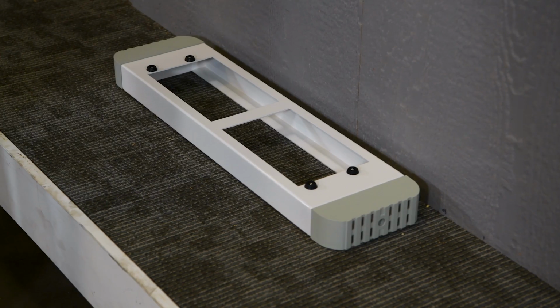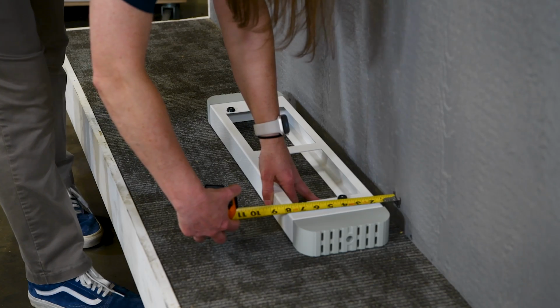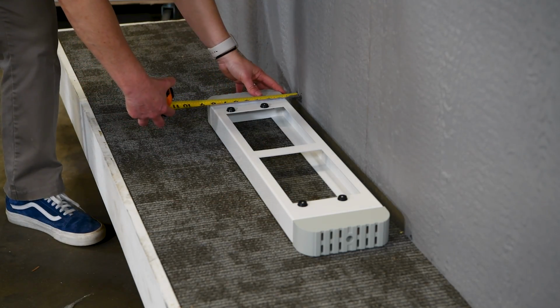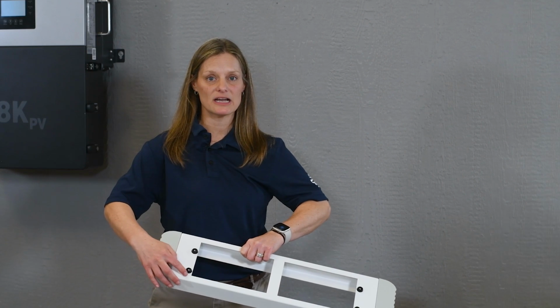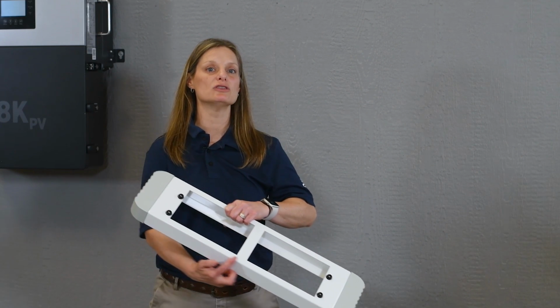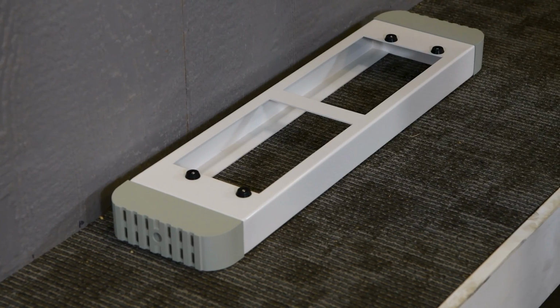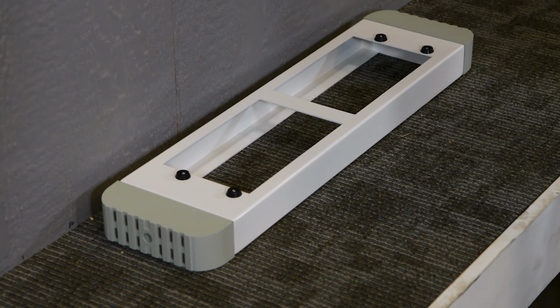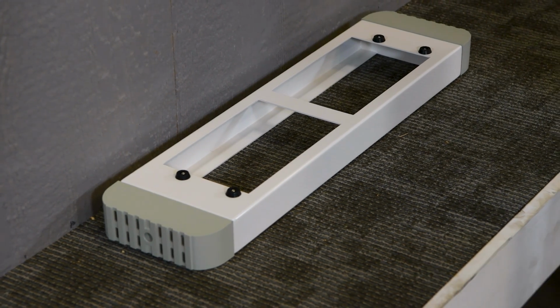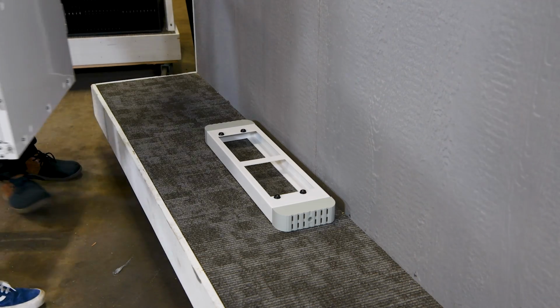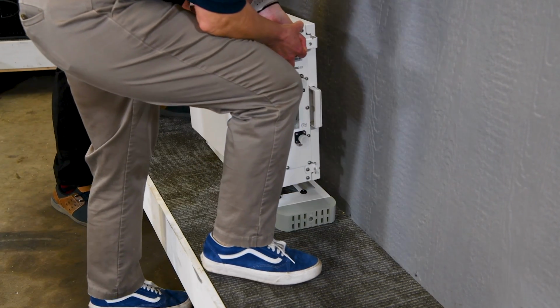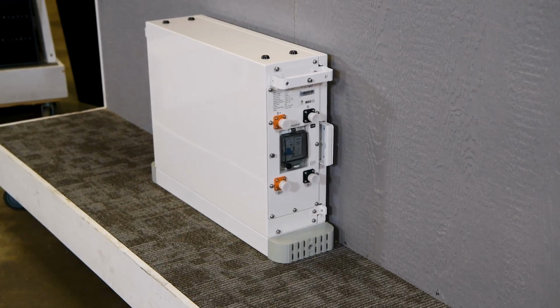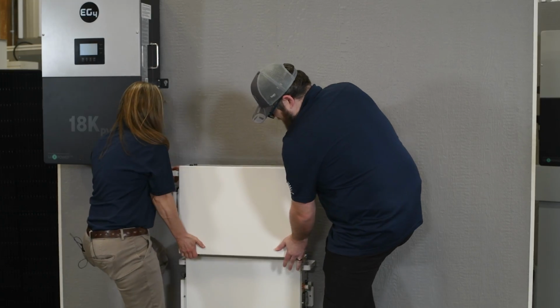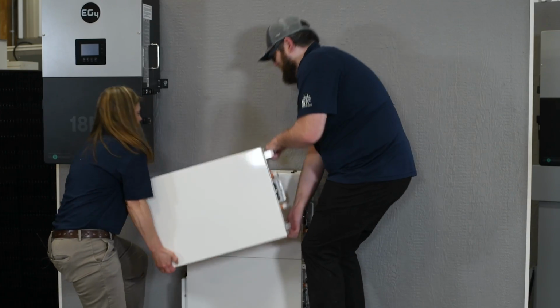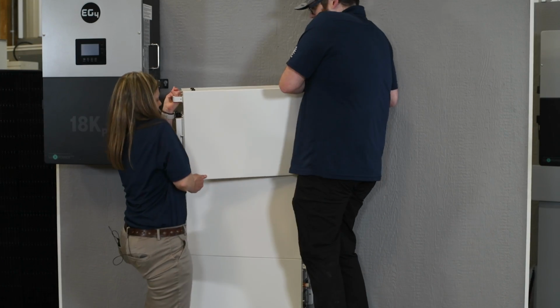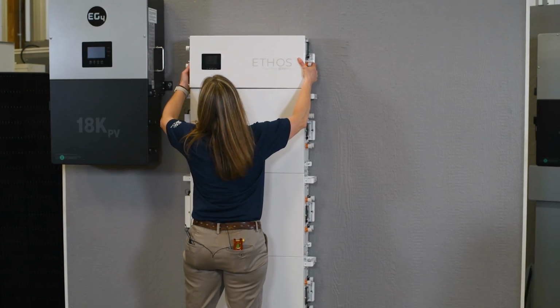So we'll begin by placing the bottom base on the floor, ensuring it's about 1.2 inches away from the wall. The rubber stoppers on the base are designed to support and align your battery modules as you stack them. Position the base so that the stoppers, which are closer to the edge, face the front. Next, grab one of your batteries, place it on top of the bottom base, ensuring it sits securely on the rubber mounts. Continue stacking battery modules on the top of the base, adding up to 3 in total. Once these are in place, position the controller box on top.